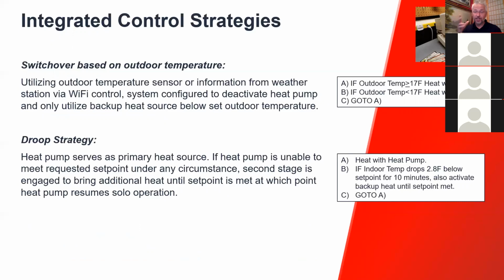There's really two strategies, and these are highlighted very well in the guidance that came out in New York State. One of them is a switchover based on outdoor temperature, and the other one is a droop strategy. In the New York State example, you can use one strategy or both strategies, either or. And in Massachusetts, early on, they started out advocating for a combination of strategies, but they recommended having a switchover temperature relatively warm. And honestly, we've seen examples in Massachusetts where that just caused real big problems for consumers.